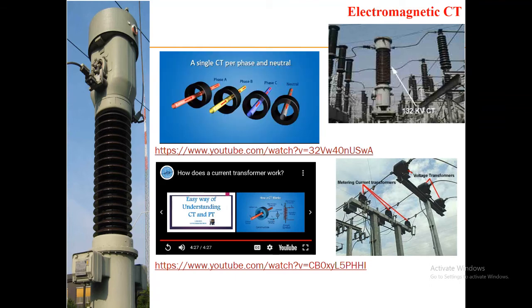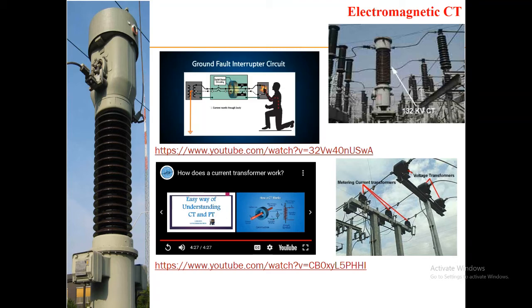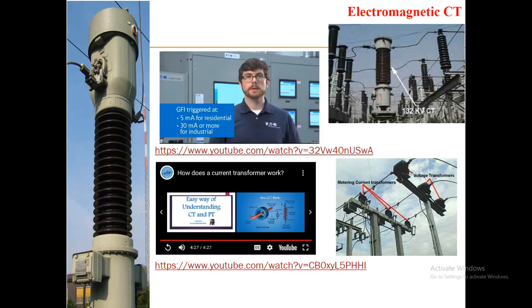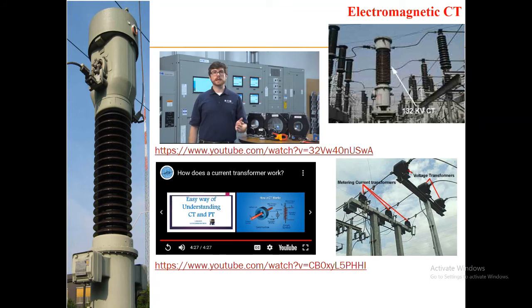A single CT is generally needed for each phase and neutral to monitor current. But for ground fault protection, a special type of CT is used. All of the phases and neutral conductors go through the ground fault CT, and if any residual current exists, in other words current comes in on one of the phases but doesn't return on the other phases or neutral, then there is a ground fault. In your house, this is triggered by a 5 milliamp level, and in industrial applications this may be 30 milliamps or even a couple hundred amps. Ground fault protection is generally for personnel safety in homes and equipment protection in industrial applications.